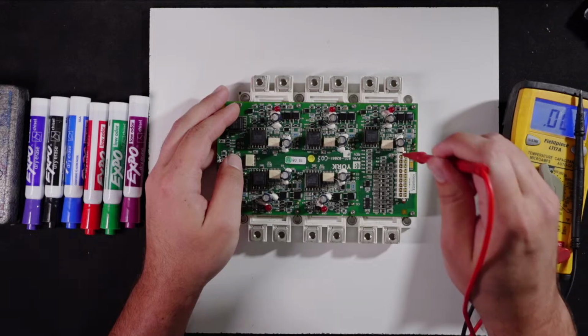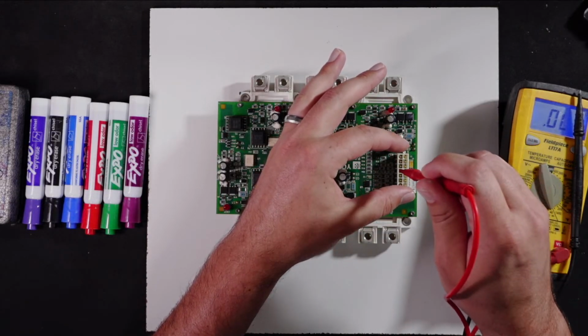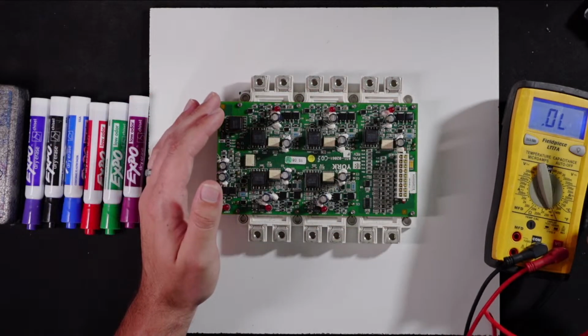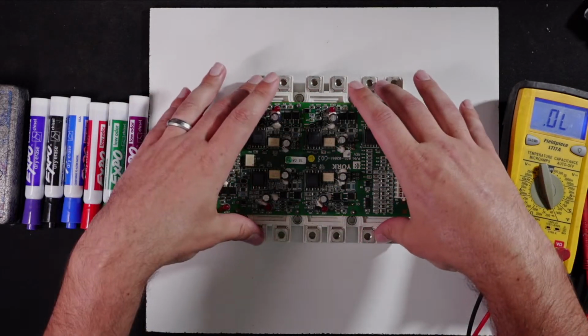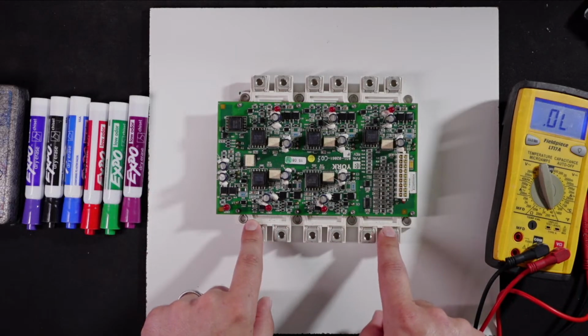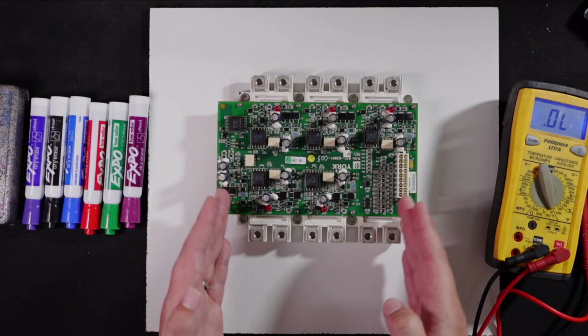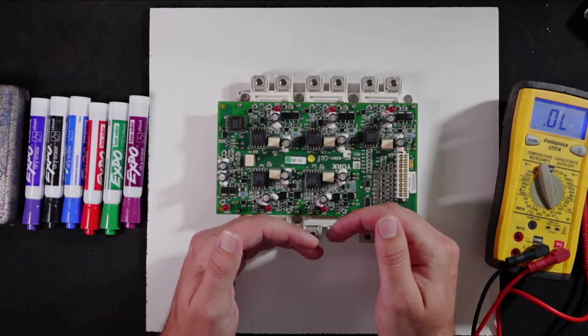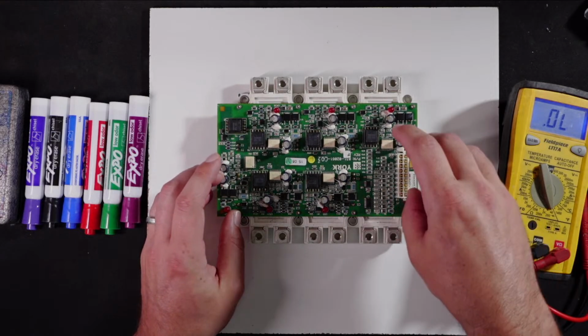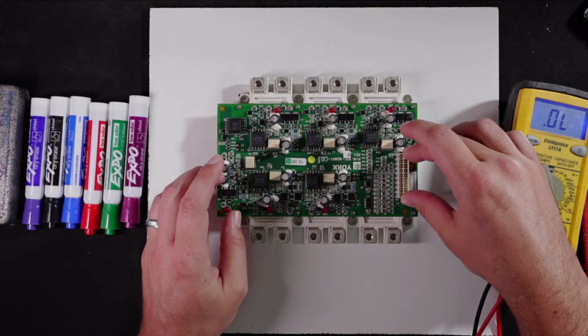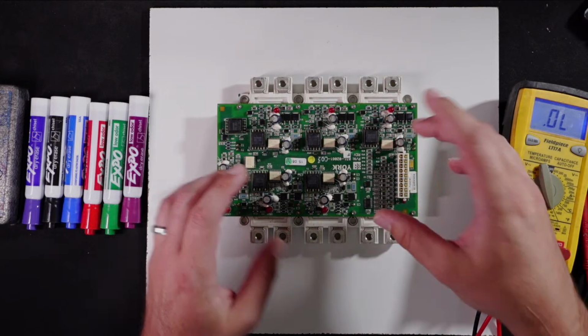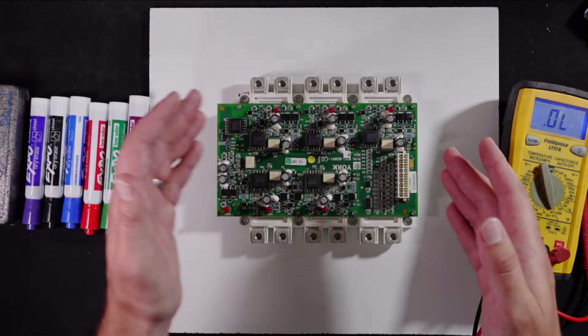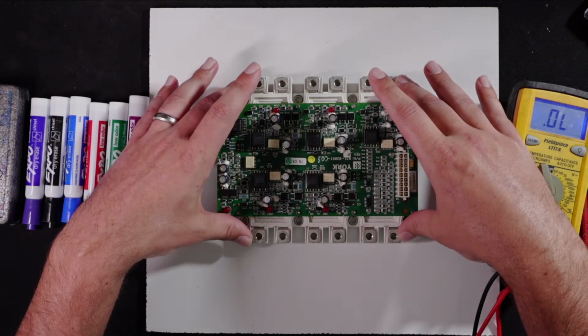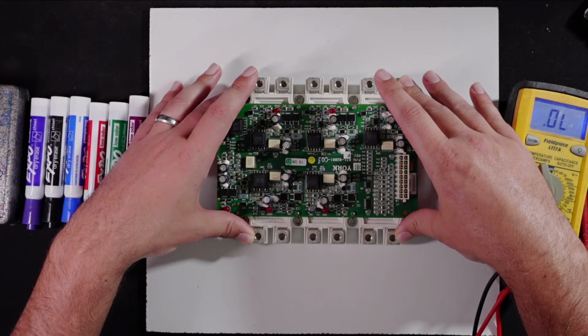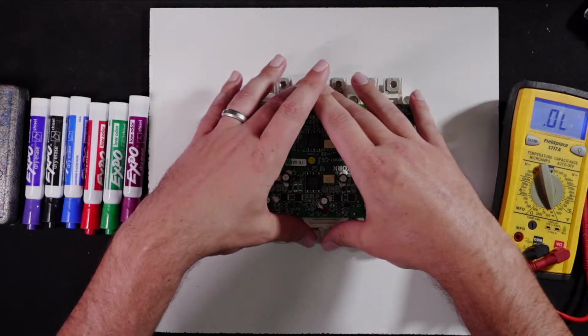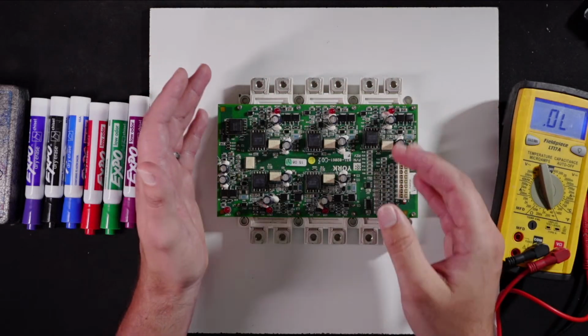Even if you use your meter lead, when the plug's in there, actually making sure that each of those pins is fully depressed is an important troubleshooting step, because that can cause instability here. These three gates have to work in sequence, whether they're individual legs or one common leg. They have to work in sequence with each other. To get that sequence perfect, we have to make sure we have a solid connection here. So that's where this Molex point becomes an extremely common failure point, because we don't have a solid enough connection to properly control these three modules in sequence with one another.